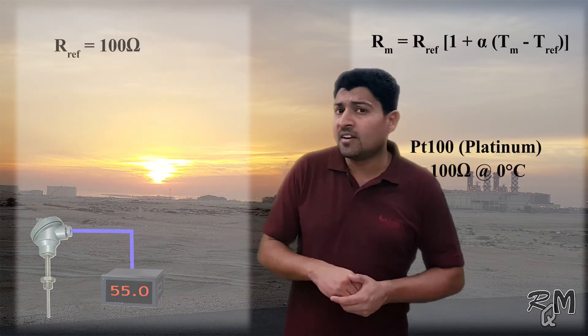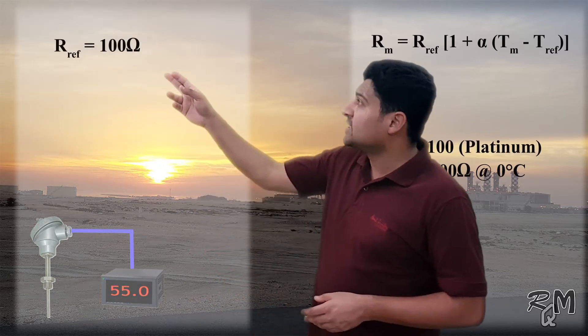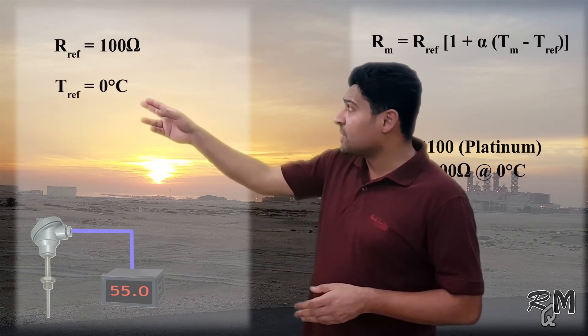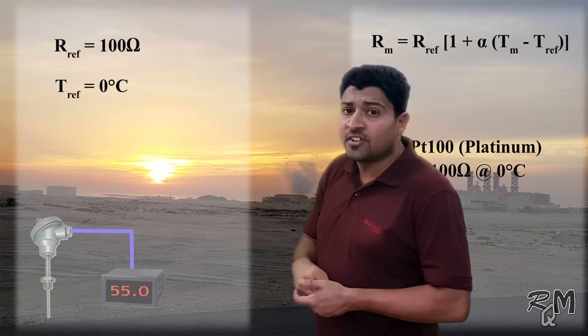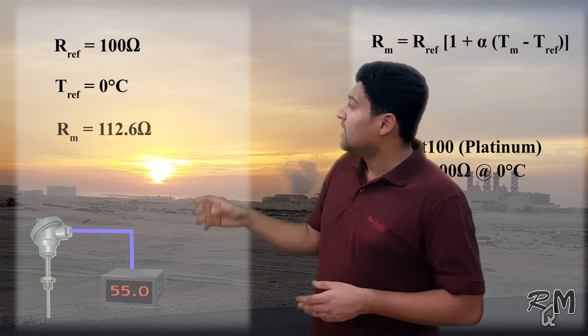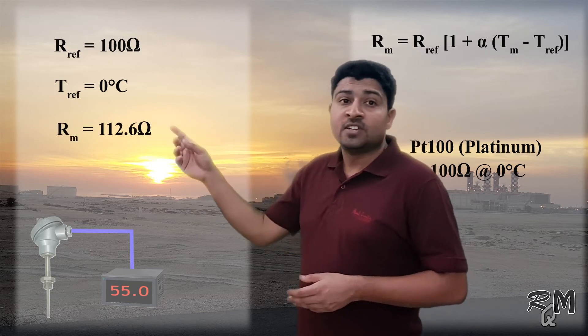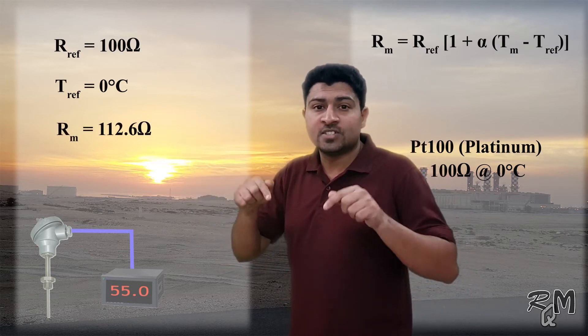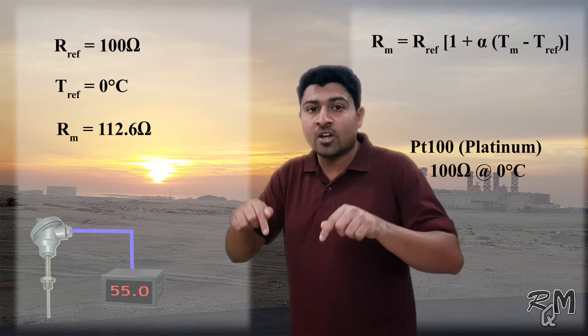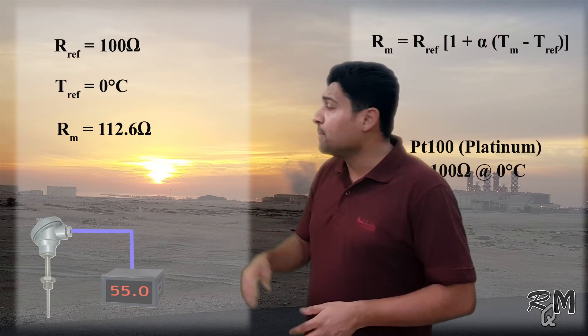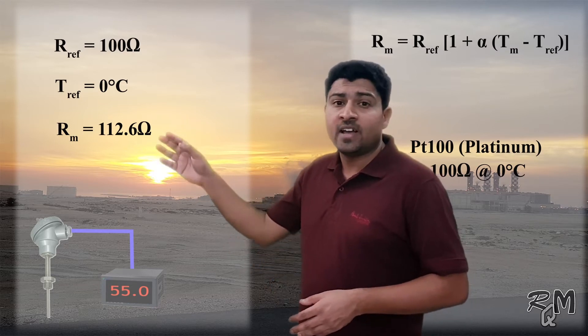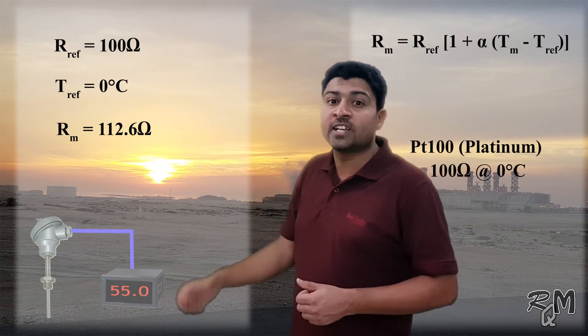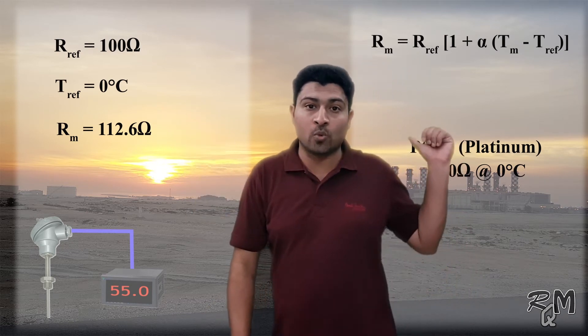In PT100, the reference resistance is equal to 100 ohms. The reference temperature is equal to 0 degrees centigrade. The measuring resistance — this is the resistance which we want to measure, it is the resistance which we are measuring on the terminal of the RTD. I am considering it 112.6 ohms to avoid a round figure and to check the accuracy of the equation.